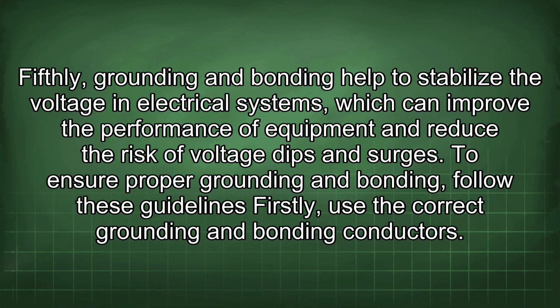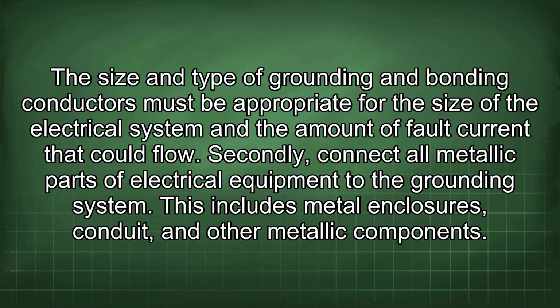To ensure proper grounding and bonding, follow these guidelines. Firstly, use the correct grounding and bonding conductors. The size and type of grounding and bonding conductors must be appropriate for the size of the electrical system and the amount of fault current that could flow. Secondly, connect all metallic parts of electrical equipment to the grounding system. This includes metal enclosures, conduit, and other metallic components.